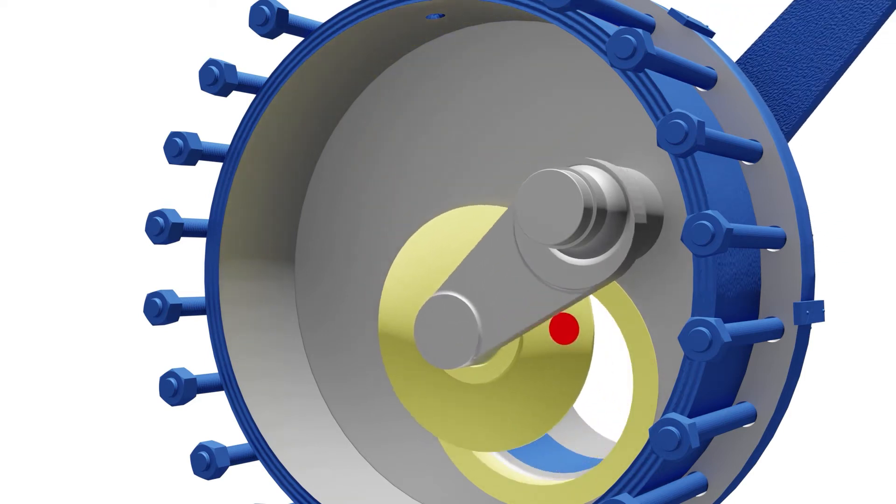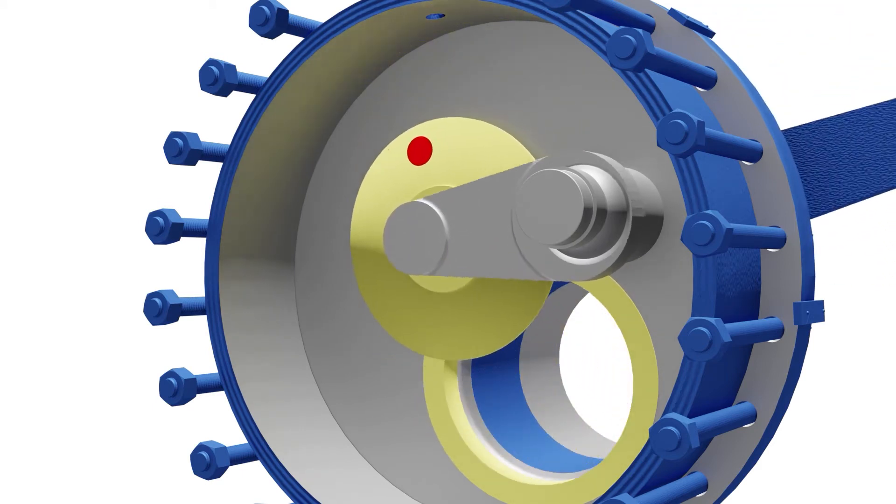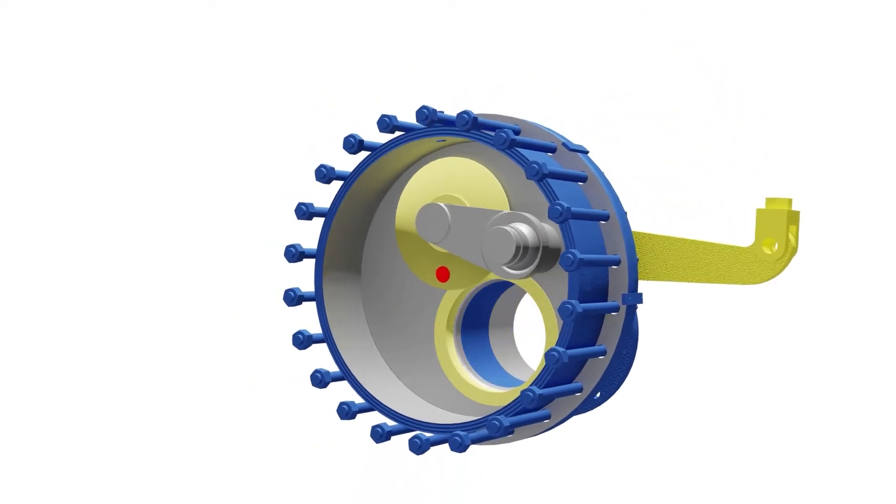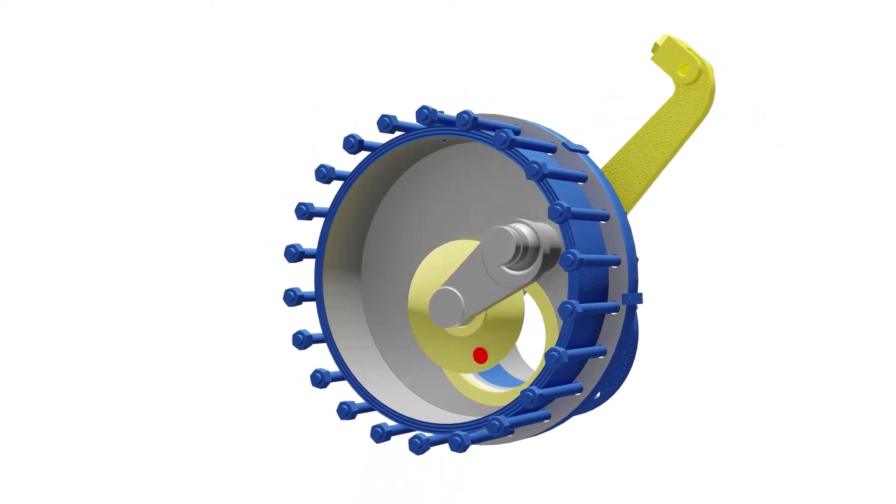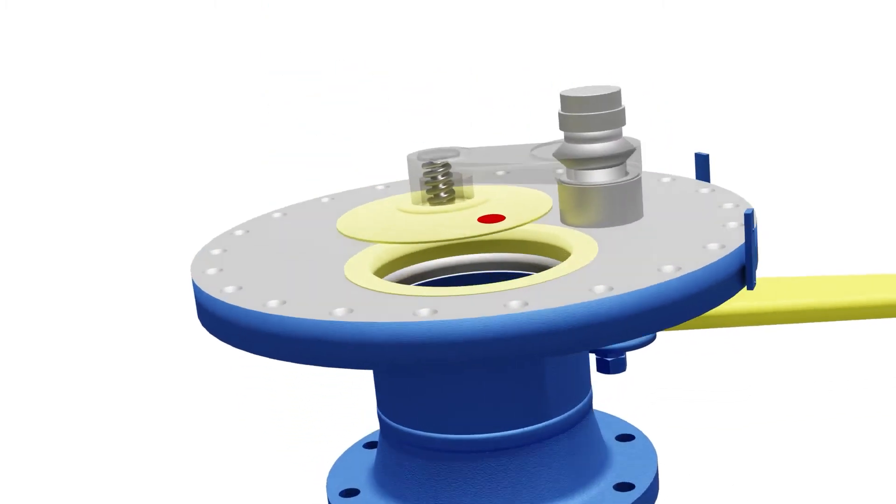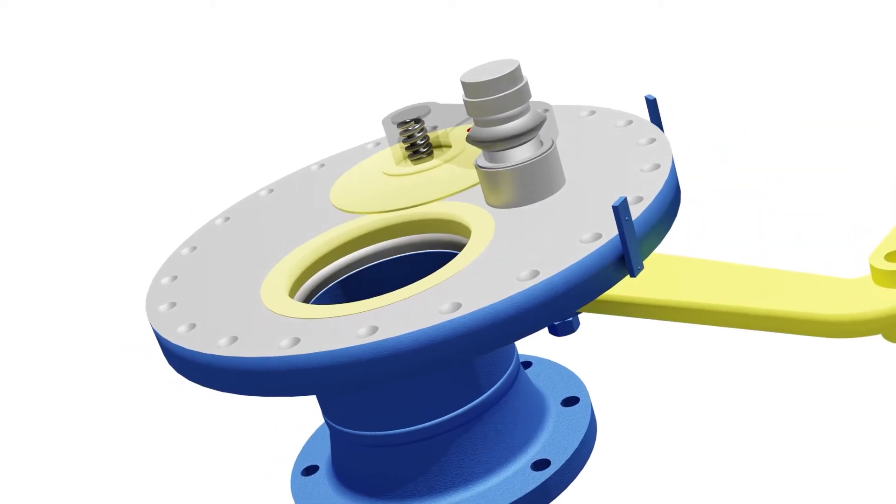We call this overlap wideband seating, which aids in the valve's sealing capabilities. The lever arm in the ProValve moves the disc in an arc from open to close and vice versa. Due to the spring loading the disc, media is prevented from getting between the disc and seat, and the disc remains in intimate contact throughout the stroke of the valve.